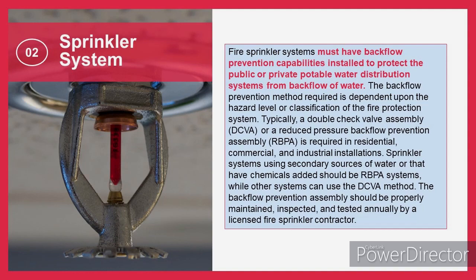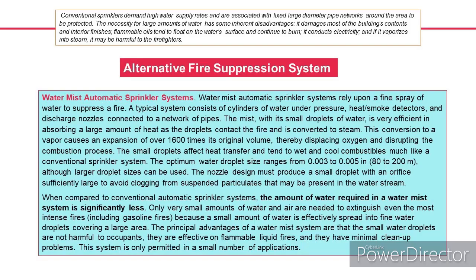Conventional sprinklers demand high water supply rates and are associated with fixed large diameter pipe networks around the area to be protected. The necessity for large amounts of water has some inherent disadvantages. It damages most of the building's contents and interior finishes. Flammable oils tend to float on the water's surface and continue to burn. It conducts electricity, and if it vaporizes into steam, it may be harmful to the firefighters. Therefore, an alternative fire suppression system is introduced.